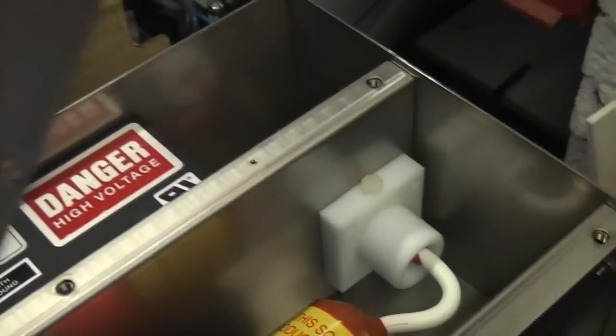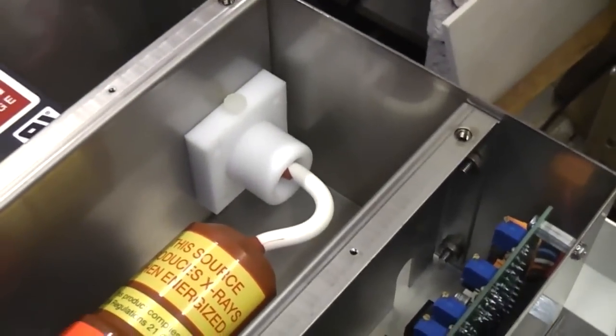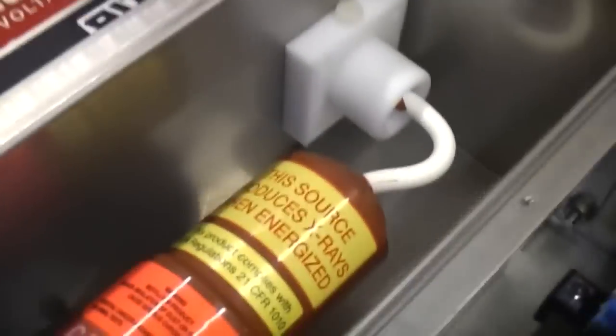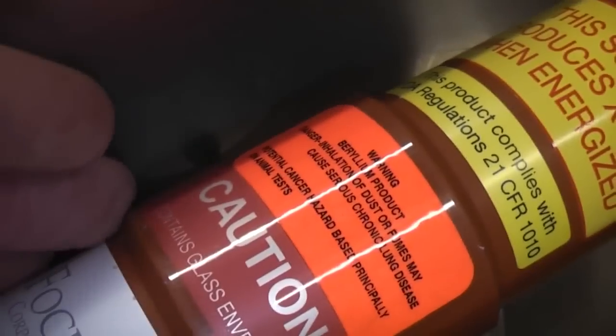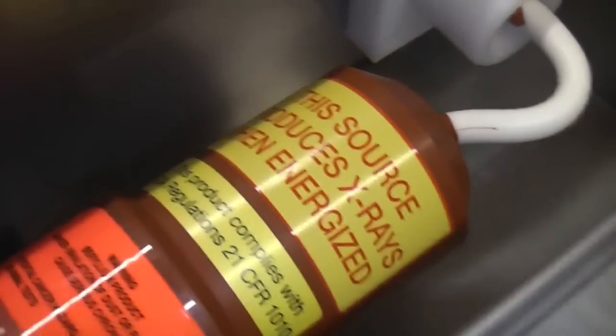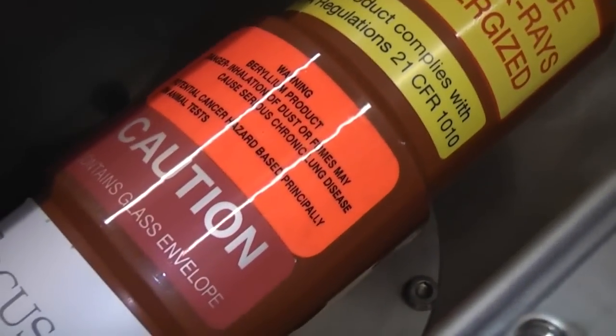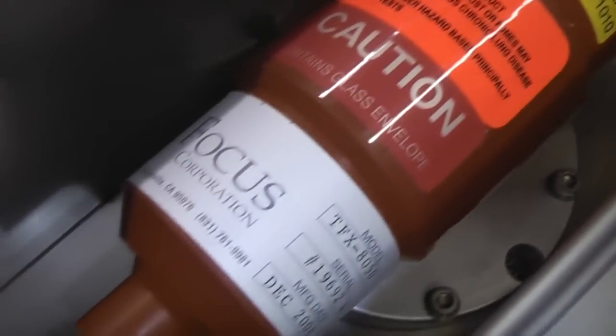So if we look under here, incidentally this cover isn't lead, it feels like stainless steel because it's only 35 kV. That has very low penetration through metal, so you don't need lead to do the shielding. So here we have the actual tube. It's got this high voltage feed through here, and the actual tube, this feels like it's coated in something like silicone, so they probably just encapsulated the whole thing in silicone to avoid any high voltage issues.